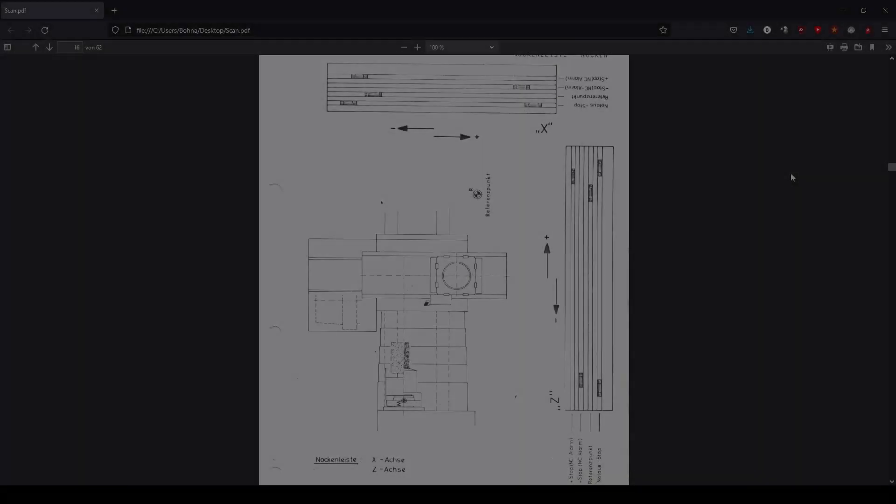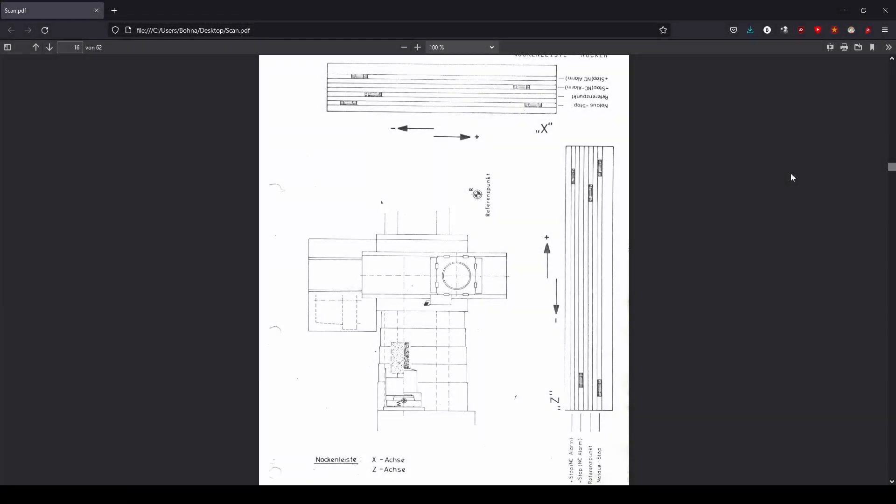The machine has different kinds of switches and other sensors installed at many points in the machine in order to obtain feedback on the status of the machine. When the machine is switched on it is not known at first where exactly the axes are located since no absolute encoders are installed. Therefore a homing procedure is run at the beginning by slowly moving the axes in one direction until they reach a reference switch. From here the controller can calculate the distance relative to this point and now knows the exact position of the axes.